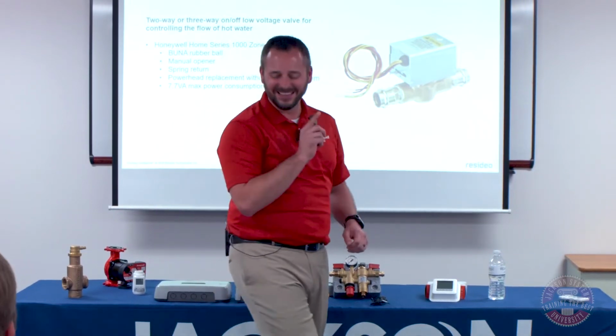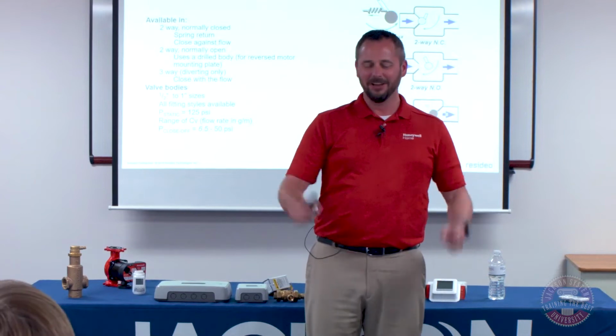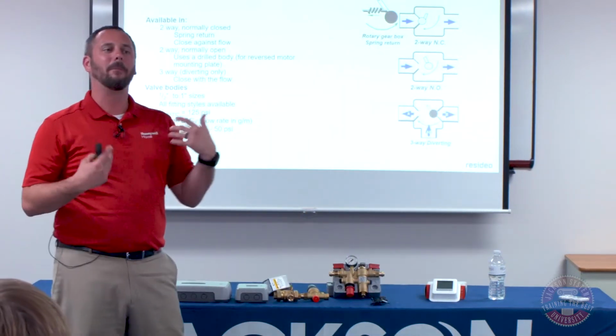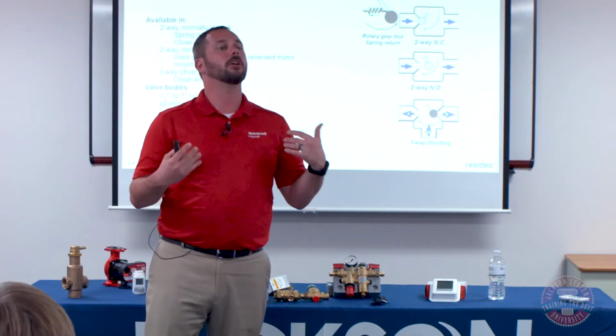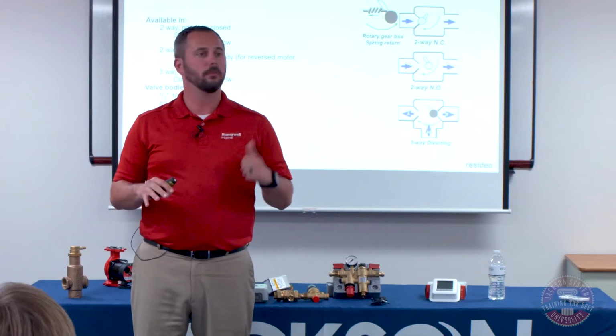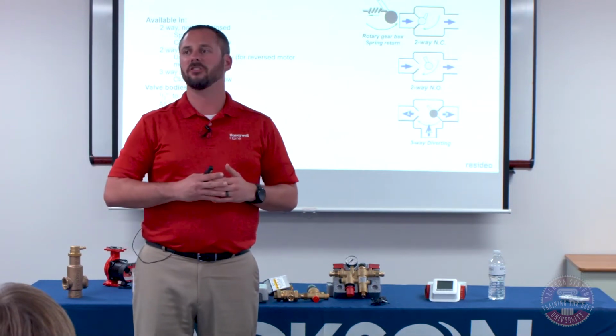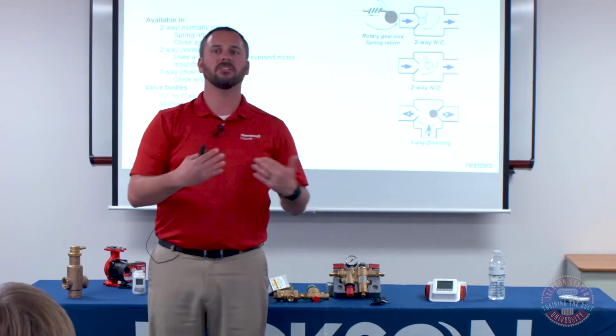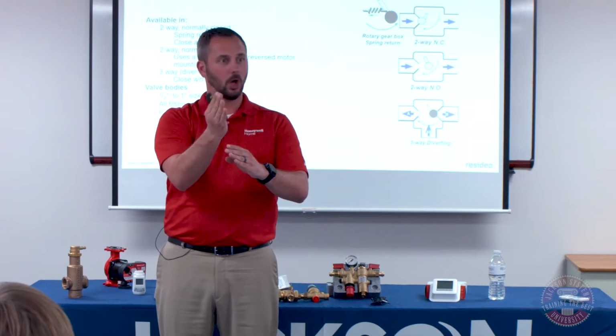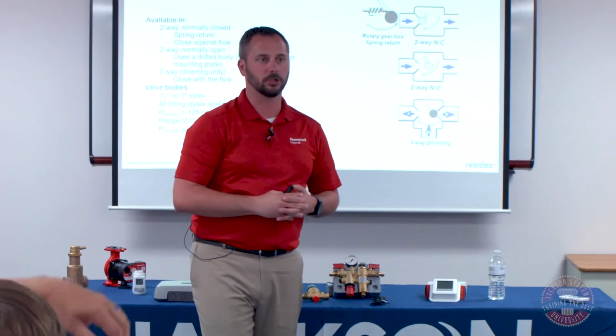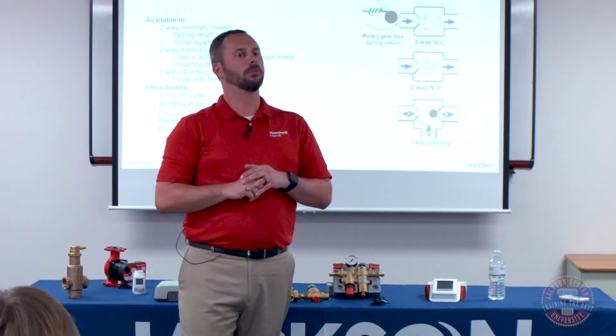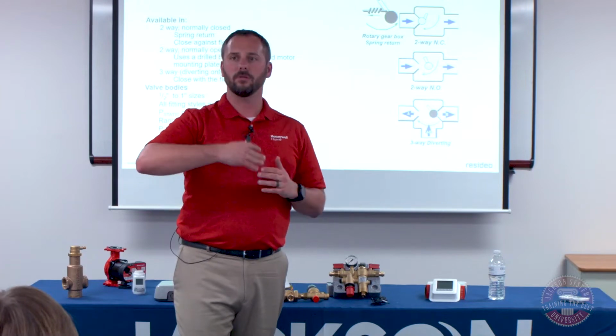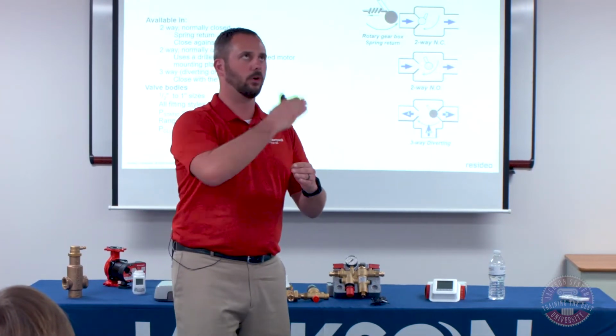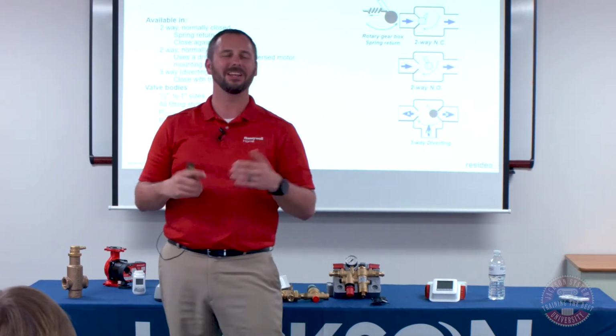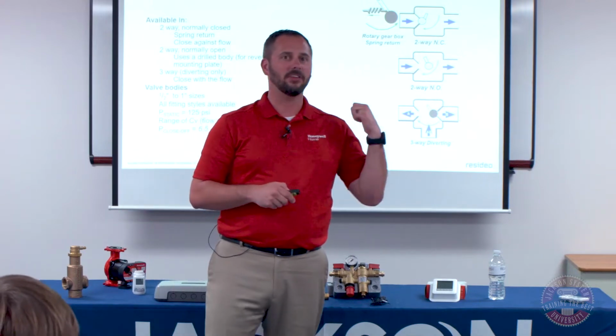All right. Good questions, though. Because I did say normally closed, let me jump to a slide. Here are our different configurations. We've got normally open, normally closed, and we also have diverting valves. Again, diverting valves and mixing valves are two different valves. They're both three ways, but in a diverting valve, you're literally just diverting water from one direction to the other. In a mixing valve, you're proportionally adjusting the flow of water from one side to the other depending on the outlet temperature. We have both, but in this series of valve, these are only diverting because they're 24-volt open, 24-volt close, or 24-volt close, 24-volt open, depending on the configuration ordered. And we've got these in 1/2 inch through 1 inch.